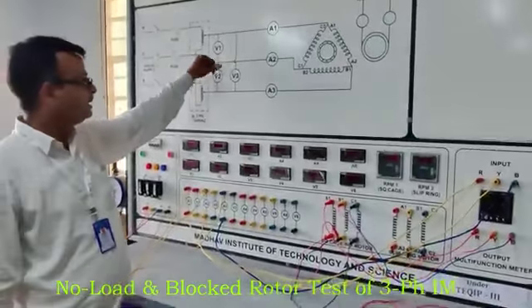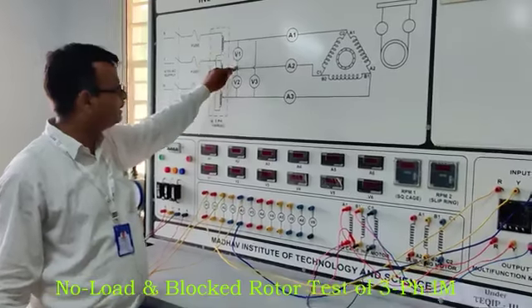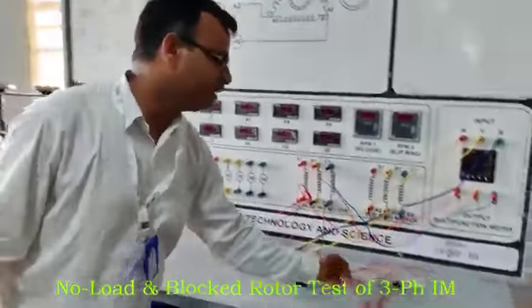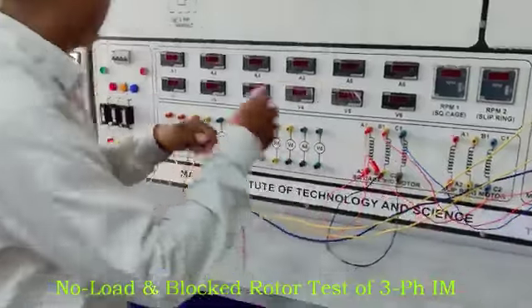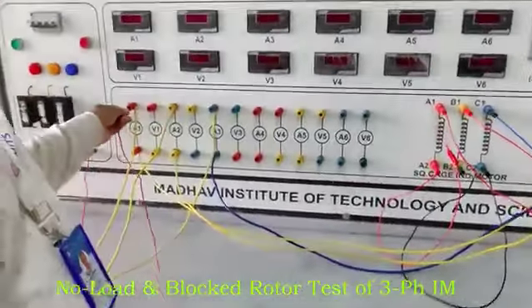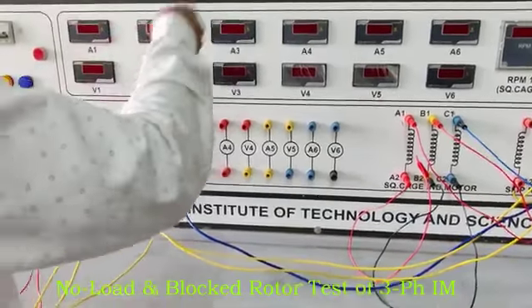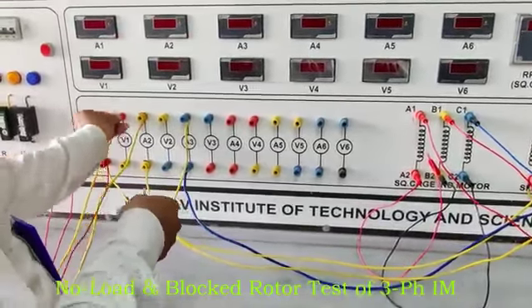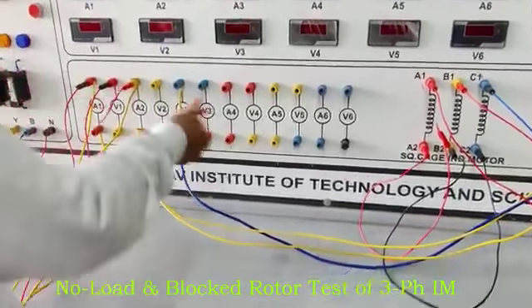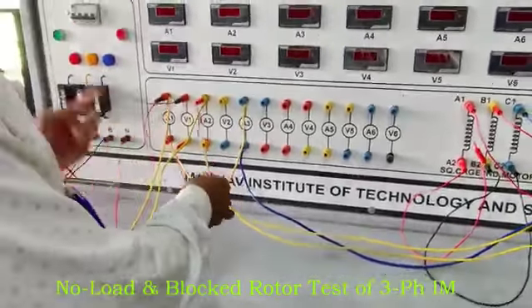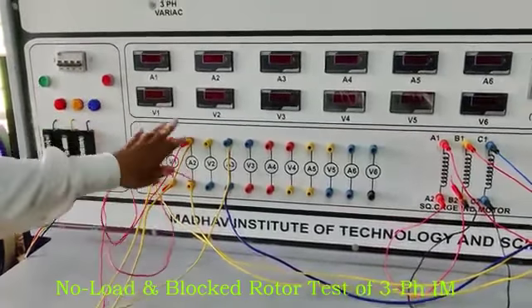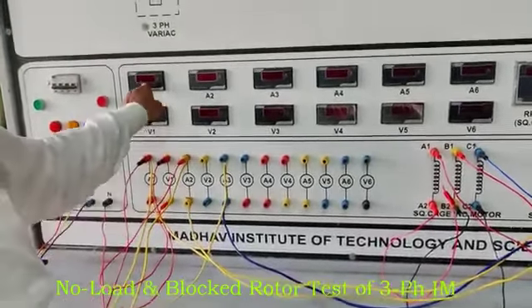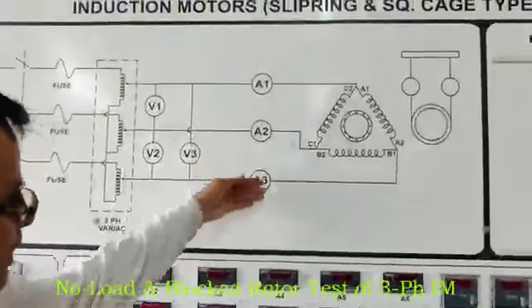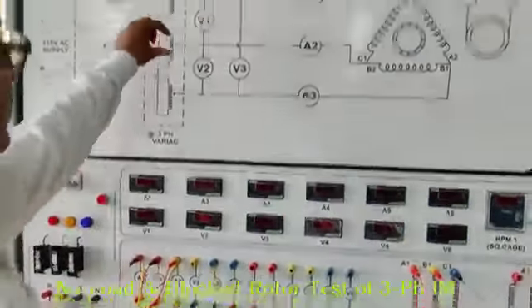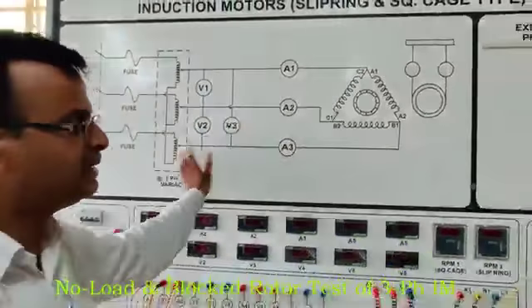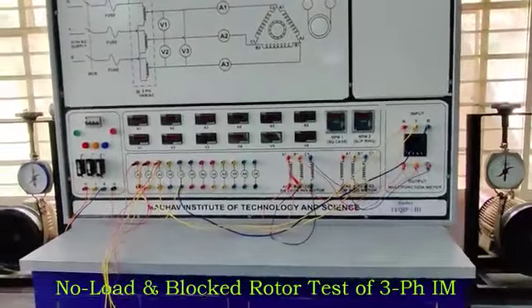And second thing, we have to connect a voltmeter here. We connect the voltmeter across two lines for measuring line to line voltage. Line to line voltage means you will connect in these positions. There are two lines, A1 and A2, V1. So we have to connect V1 terminals. In that case, we have to observe the readings of A1, A2, A3 for determining the line current, and V1 voltmeter for measuring the voltage. So this is the complete circuit for performing the no load test.